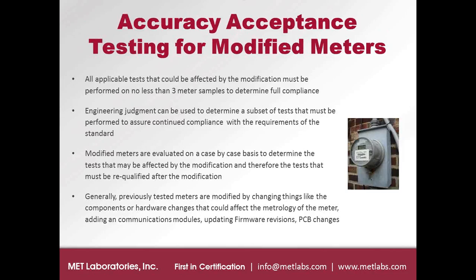So once you've gone through the initial program, again, if you have modifications to the meter, I touched on this earlier, we've really got to take a look at what those modifications were. It's really a case-by-case situation, depending on the type of product and what the modification is. And we collectively get together here at MET, again, with the manufacturer's input at times as well, to come up with a good judgment on what the modification could have affected in terms of the compliance that was performed in the past. So when in doubt, we're going to request that certain tests be rerun in order to prove out that the meter is continuing to be compliant.